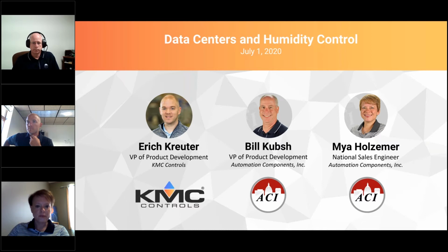Relative humidity transmitters are likely also going to be very prevalent in a data center. Again, the higher accuracies are what we'd expect to be utilized. Accuracies of maybe 2%, possibly even 1%, with or without NIST certification. And that's all just dependent on how tight of control you're trying to maintain. It's going to be a combination of relative humidity and temperature that are going to help with the dew point calculation. Again, the goals there being to keep static out of the space and also keep condensation from happening in the space.